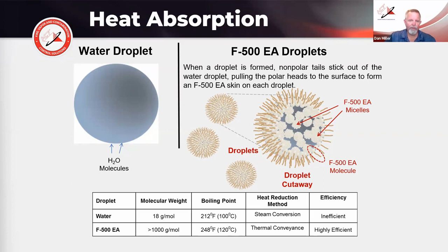A big thing it does is help absorb heat into the water droplet. That rapid heat reduction, as the F500 modified water droplet strikes the fuel or interfaces with the surface of the fuel, helps absorb heat rapidly into the water droplet and into the spherical micelles. Since those droplets are made much smaller than plain water, it absorbs heat anywhere from 10 to 30 times more effectively than plain water, depending on the fuel.